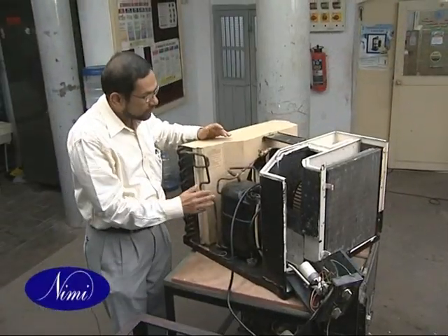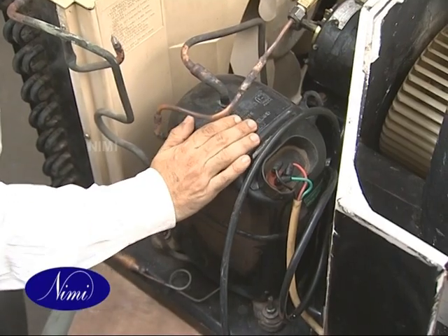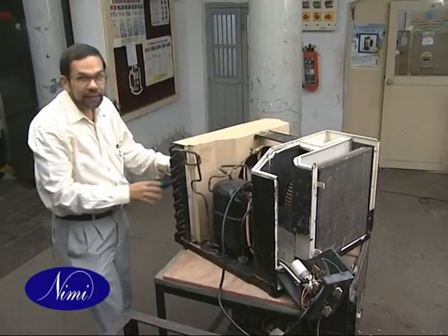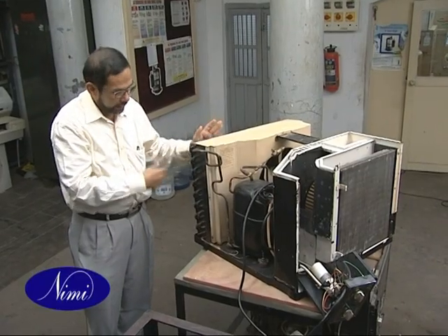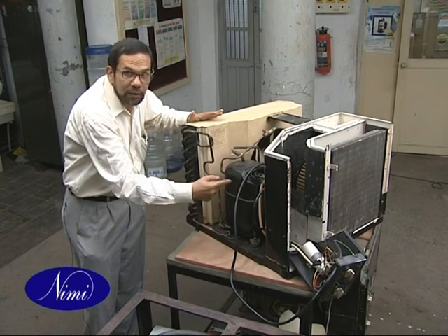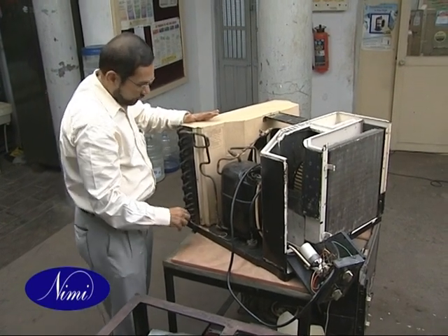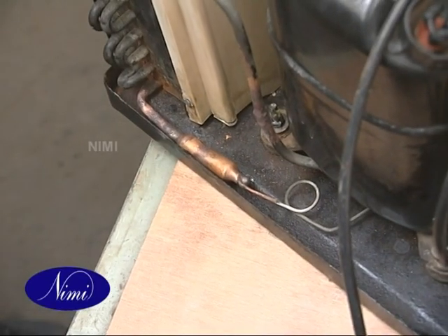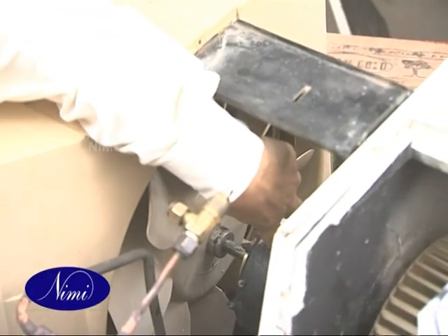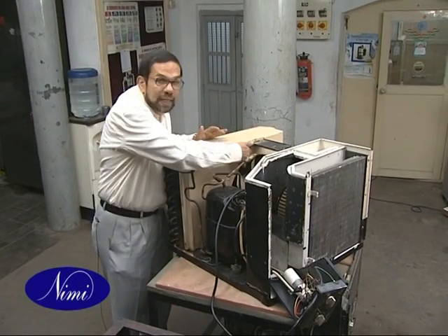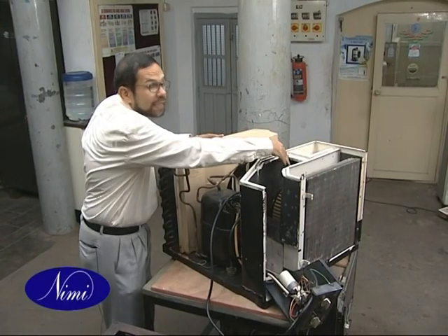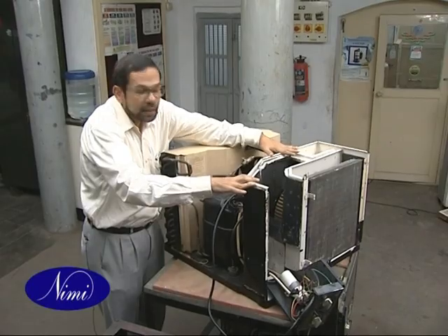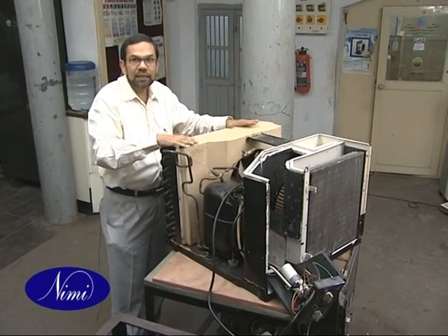The major components, like I mentioned, are the compressor, which is the heart of the system, the evaporator, which draws the heat from the room, the condenser coil, where the heat is rejected, and the capillary tube between the two. In addition, we have the strainer dryer, which is attached before the capillary. You have the fan motor, which drives the blower and the condenser. So on this side we have the condenser fan, and on this side we have the blower. Now housing the blower is the bulkhead, and around the fan is the shroud.